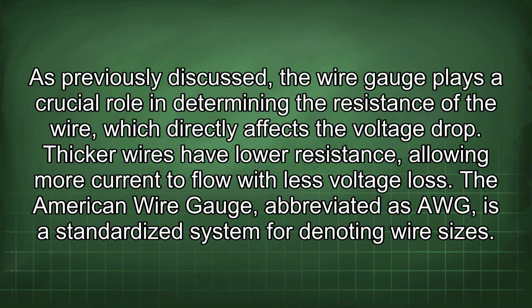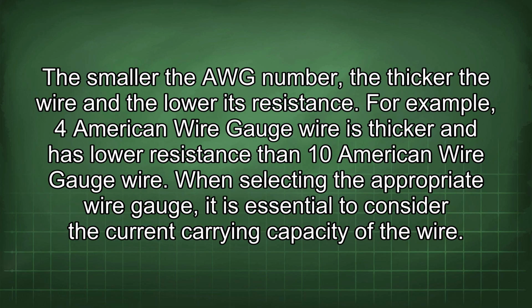As previously discussed, the wire gauge plays a crucial role in determining the resistance of the wire, which directly affects the voltage drop. Thicker wires have lower resistance, allowing more current to flow with less voltage loss. The American wire gauge, abbreviated as AWG, is a standardized system for denoting wire sizes. The smaller the AWG number, the thicker the wire and the lower its resistance. For example, 4 American wire gauge wire is thicker and has lower resistance than 10 American wire gauge wire. When selecting the appropriate wire gauge, it is essential to consider the current carrying capacity of the wire.